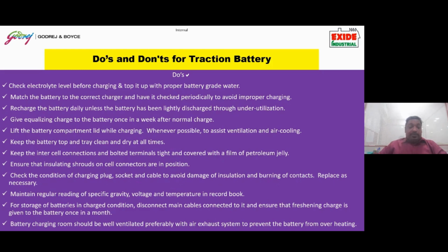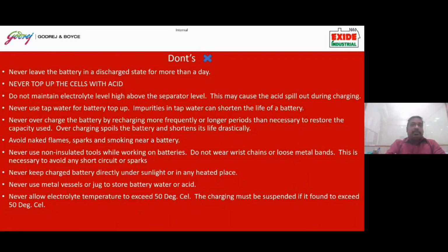So again, do's and don'ts. Do's: the battery charging room should be well ventilated with an exhaust system to prevent the accumulation of hydrogen gas, as well as to provide proper cooling to the battery and avoid overheating. Some don'ts: never leave the battery discharged beyond 24 hours. Never top up the cells with acid. If any such situation comes wherein the cells have to be topped up with acid, that should be referred to the OEM, and only the OEM person should come and carry out this activity.